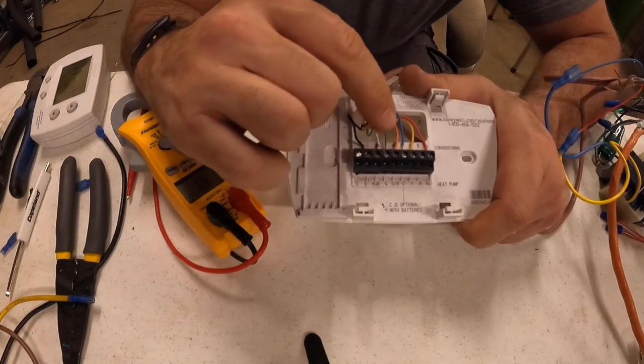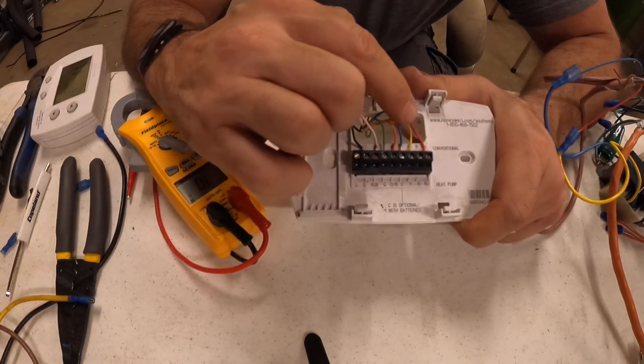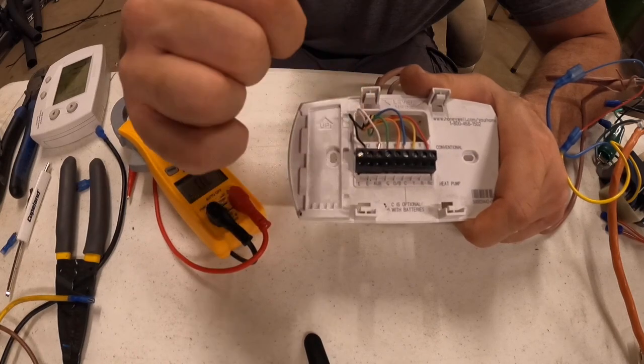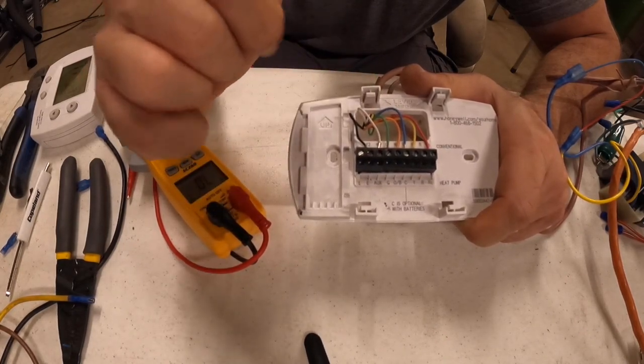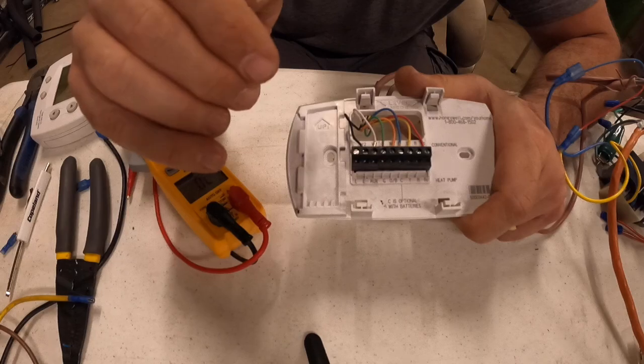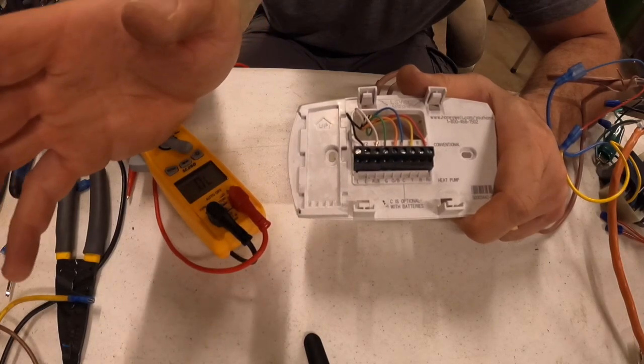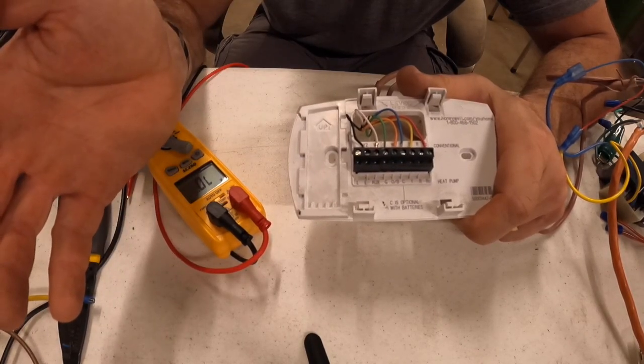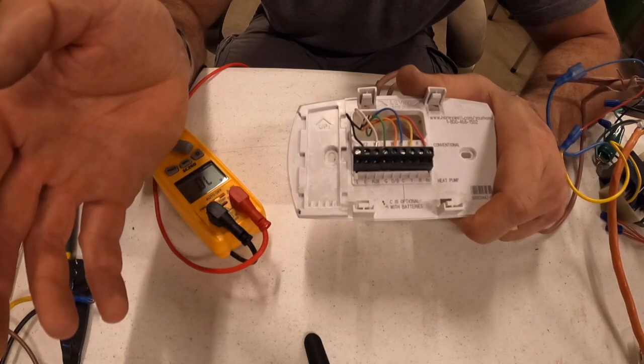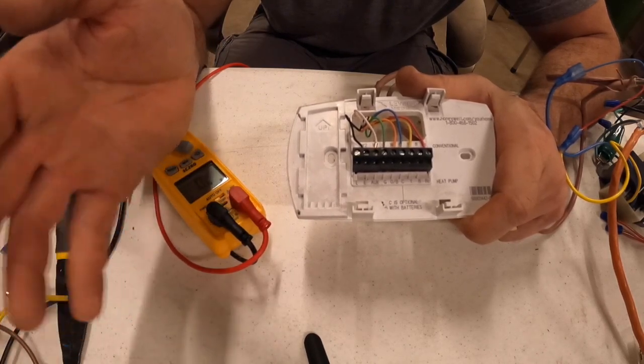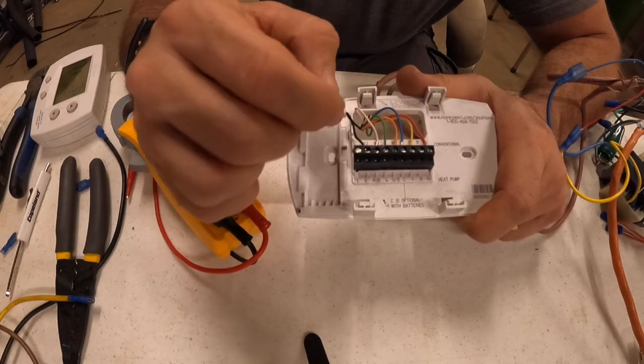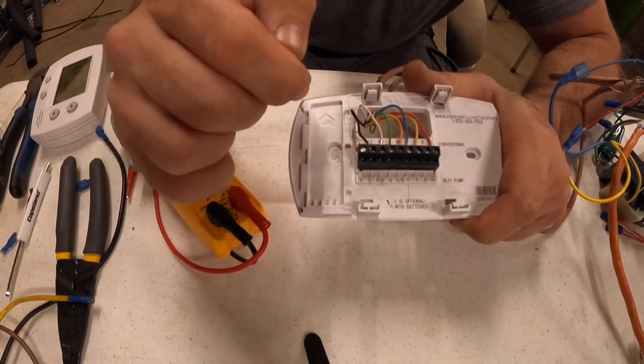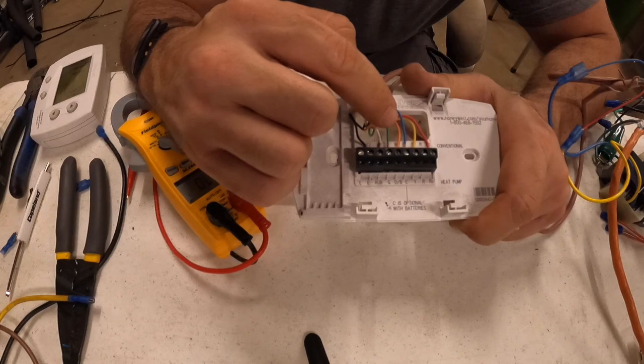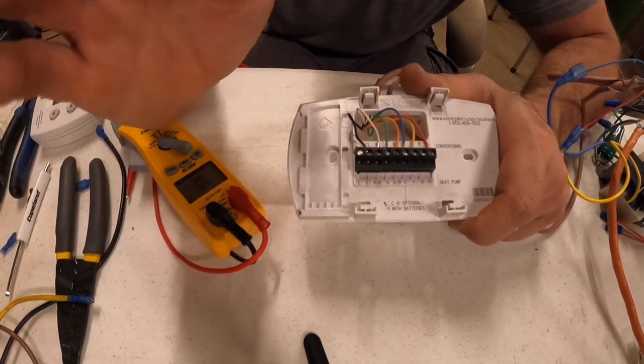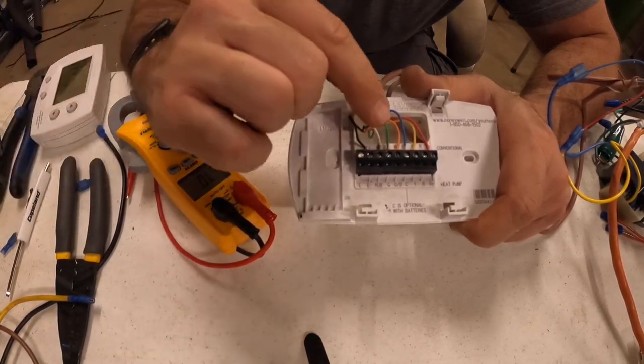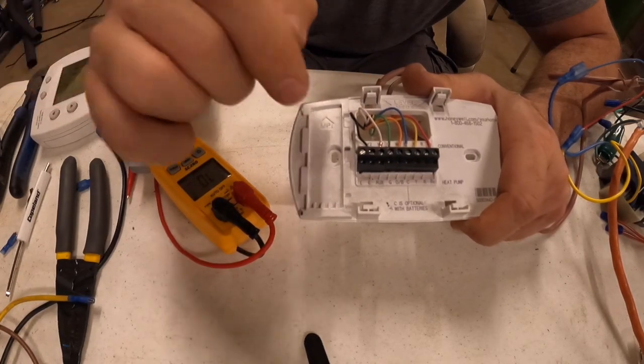Okay, so the power coming into R is going to get sent to G when there is a call for cool or heat, unless you have a furnace, then a gas furnace. Typically the furnace will turn the fan on and off when there's a call for heat. But we're using a heat pump here, so G is going to be energized basically anytime there is a call for anything, or if you call for the fan to be on.